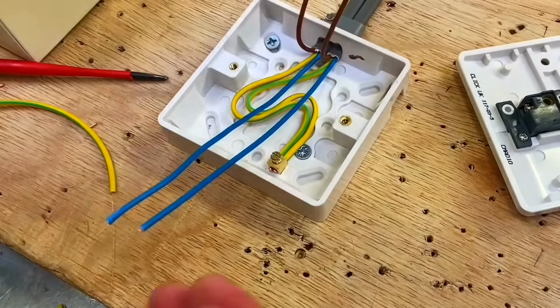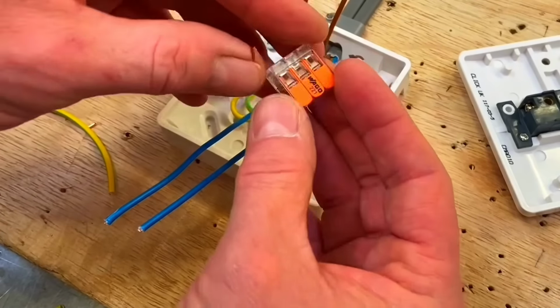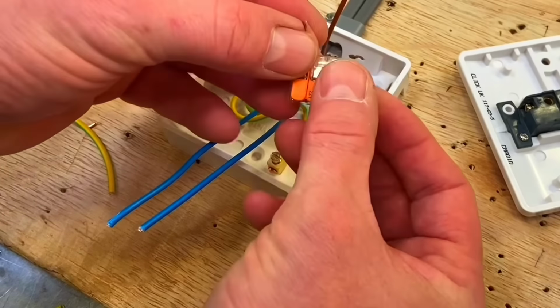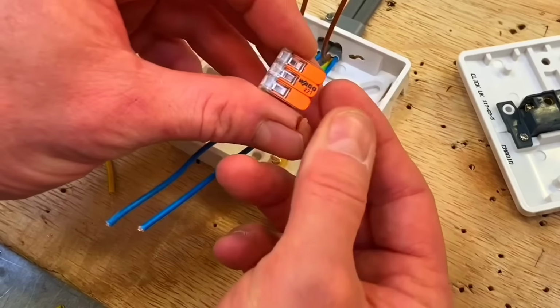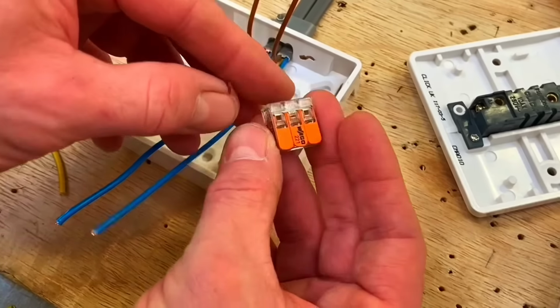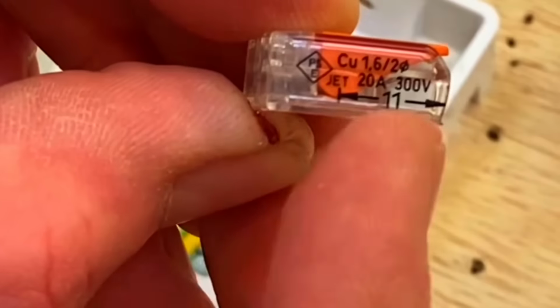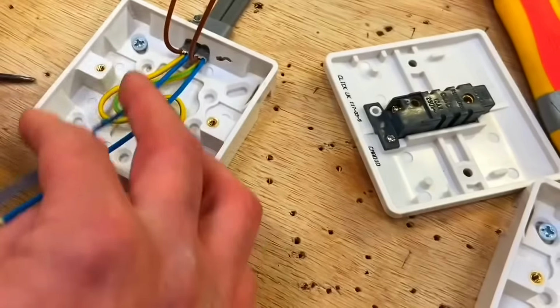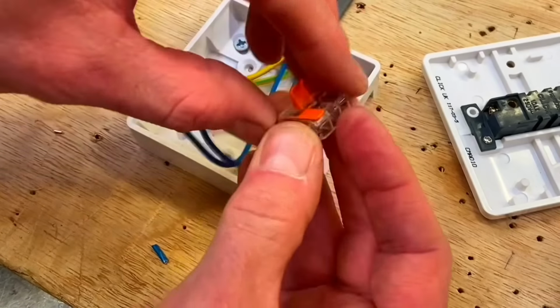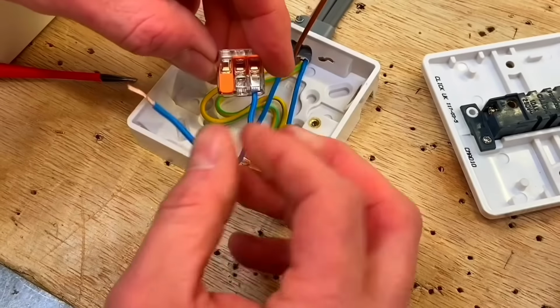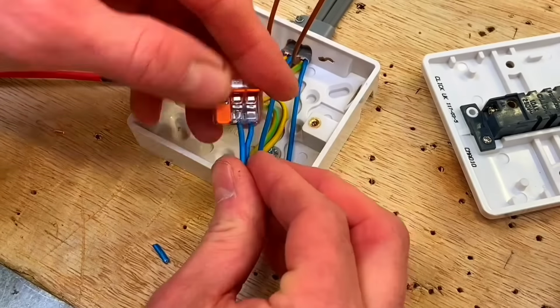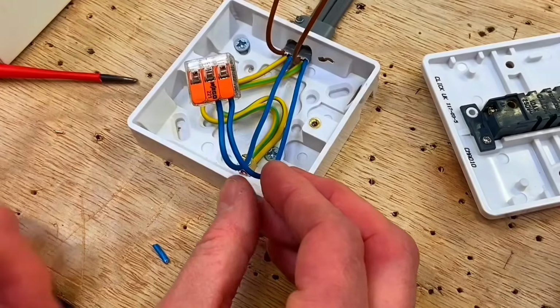And this time we're going to use our Wago. This is a 3-conductor connector. We could have had a 2-conductor connector. I just couldn't find one for the video. So we've got a 3-conductor connector here. And on the side of it, as shown in previous videos, you can see that you've got to strip back to 11 mil the insulation off the conductors themselves. Lift up the levers. Insert our conductors in like so. And then just, there we go. So they're now connected. Double these over.